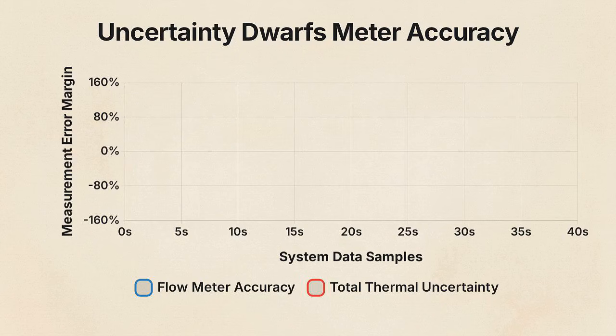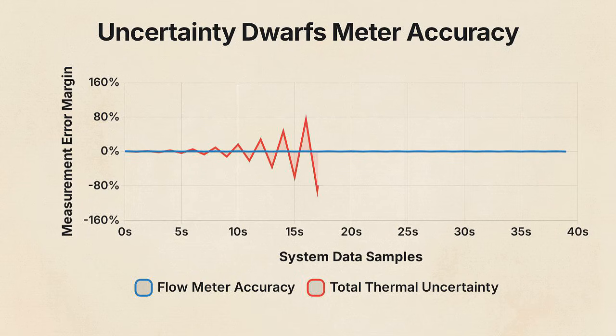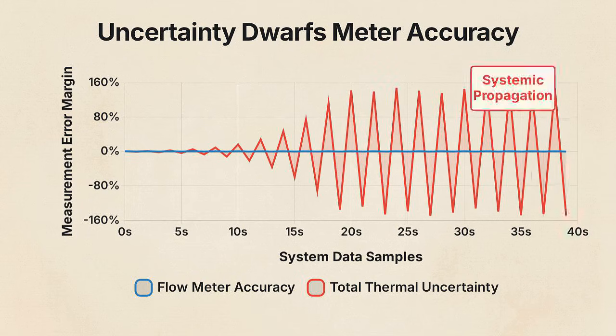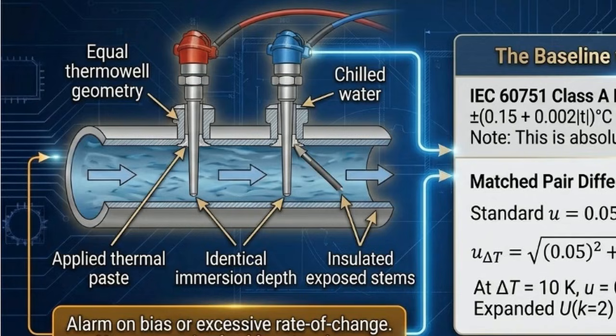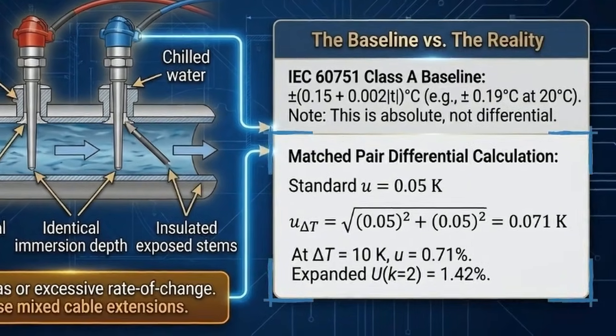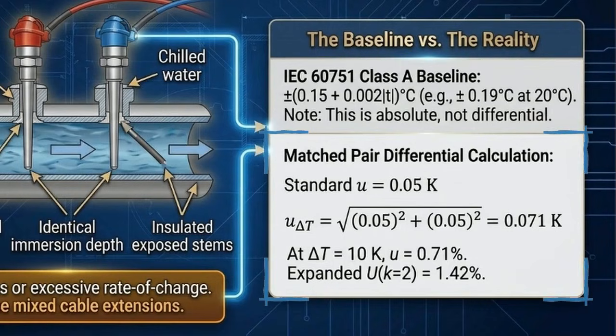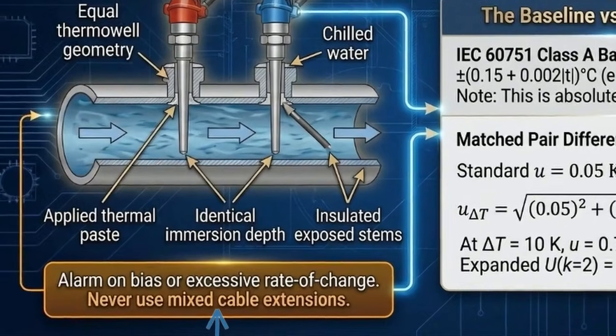However, the stated accuracy of that flow meter alone is entirely insufficient to establish the uncertainty of the total thermal duty. This diagram calculates differential temperature using matched Class A platinum RTD sensor pairs at equal depths. Evaluating sensors as a matched pair tightens the uncertainty baseline compared to absolute individual readings. Splicing or mixing cable extensions permanently corrupts the baseline data.